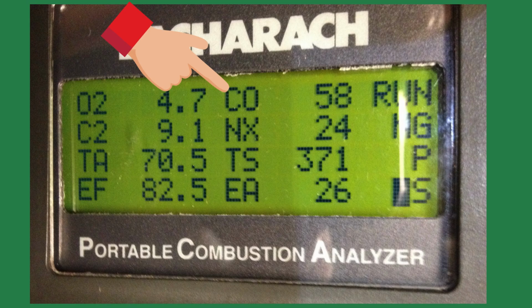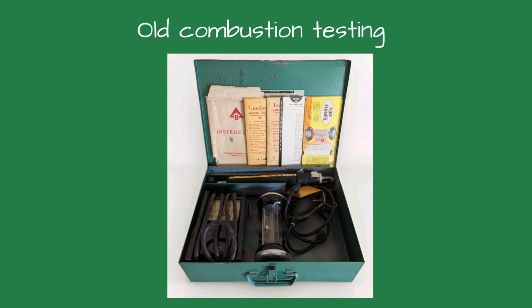For years, technicians have relied on as measured CO reading, the number that appeared directly on the analyzer screen. At first glance, it seemed reasonable. The analyzer measures the carbon monoxide in the flue gases, and the number should be the number the appliance is producing, right? Not exactly.